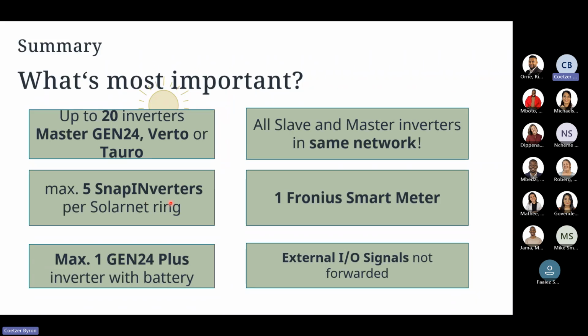So what's the summary for using the SBC? What's most important? We can have up to 20 inverters with the master being the Gen24, Verto, or Tauro. Maximum of 5 Snap inverters per Solarnet ring. Maximum of 1 Gen24 Plus inverter with a battery, as well as all slave and master inverters in the same network. Having one Fronius Smart Meter in the system is essential for using SBC. And your external IO signals are not forwarded from the master inverter onwards, for example.